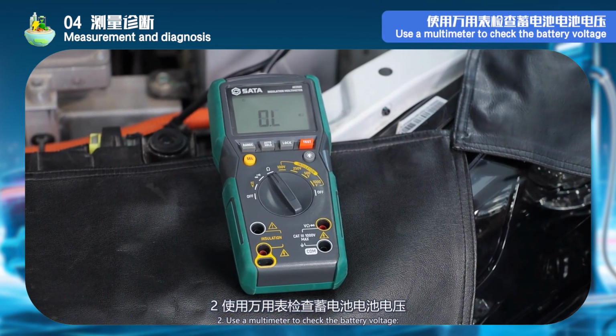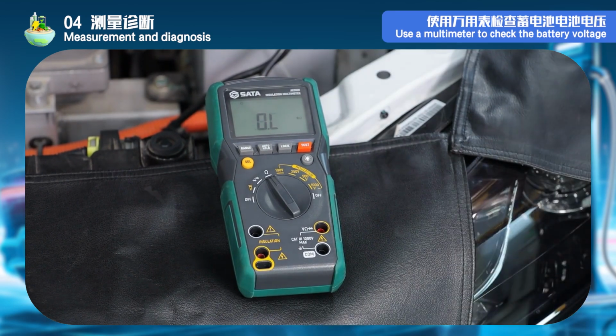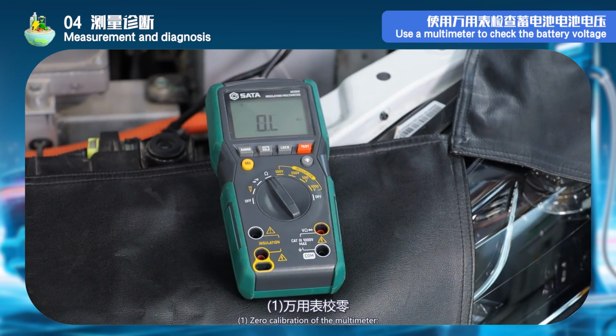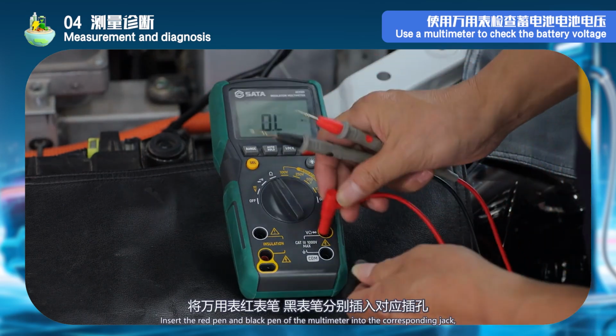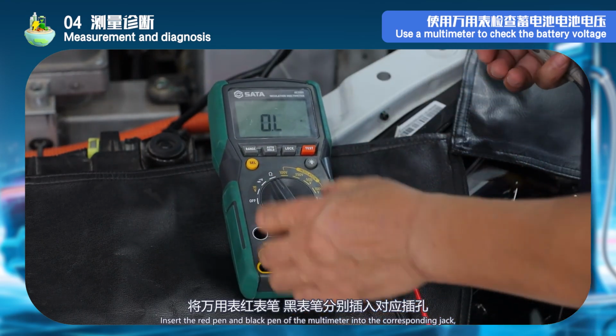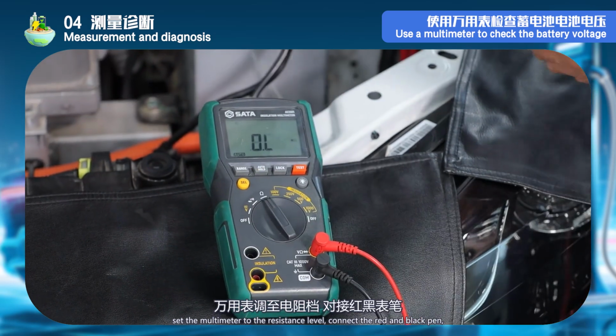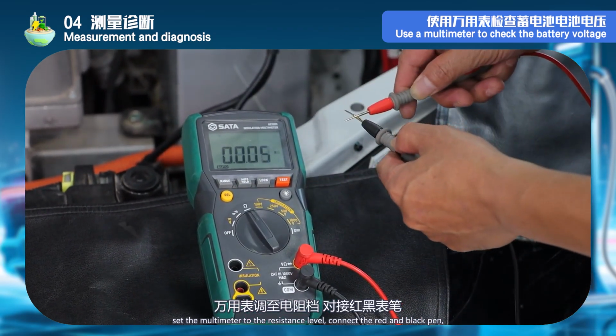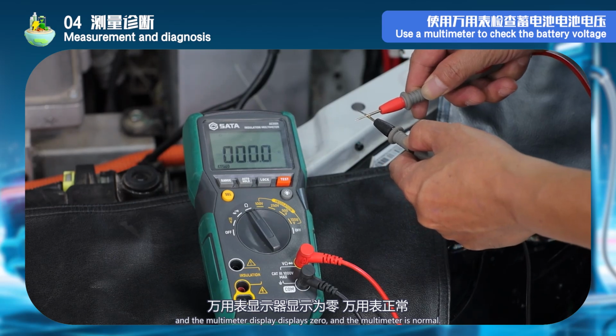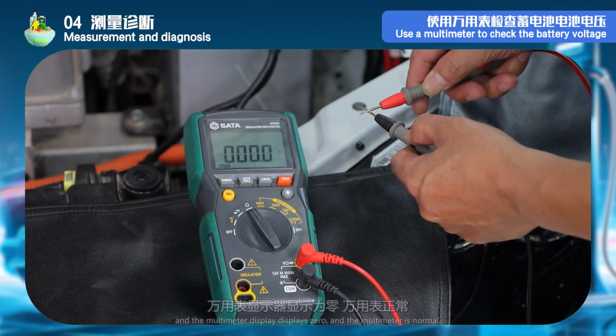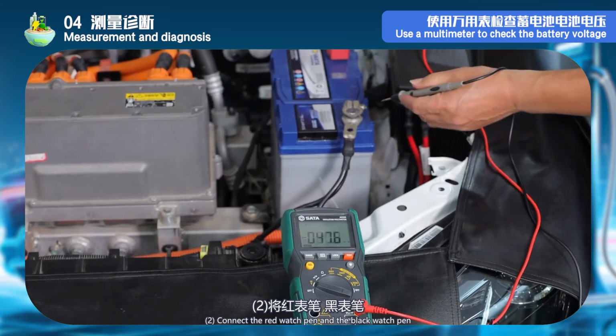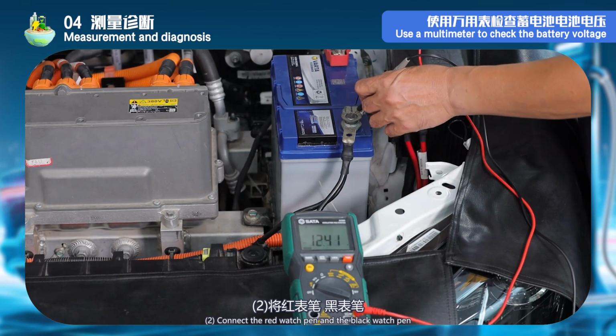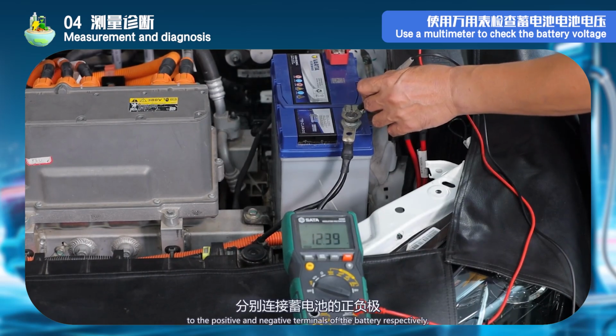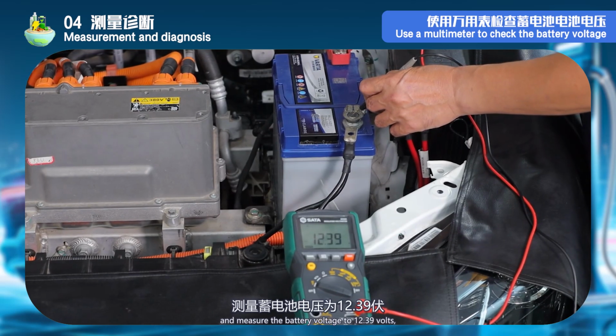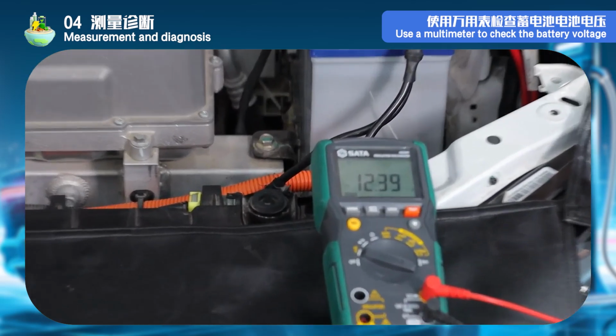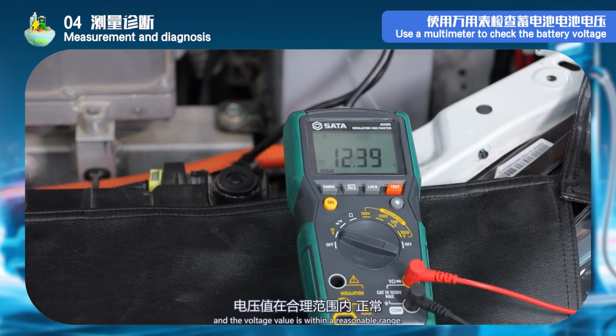2. Use a multimeter to check the battery voltage. 1. Zero calibration of the multimeter. Insert the red pen and black pen of the multimeter into the corresponding jacks. Set the multimeter to the resistance level. Connect the red and black pens, and the multimeter displays 0, so the multimeter is normal. 2. Connect the red pen and the black pen to the positive and negative terminals of the battery respectively, and measure the battery voltage as 12.39 volts, which is within a reasonable range.